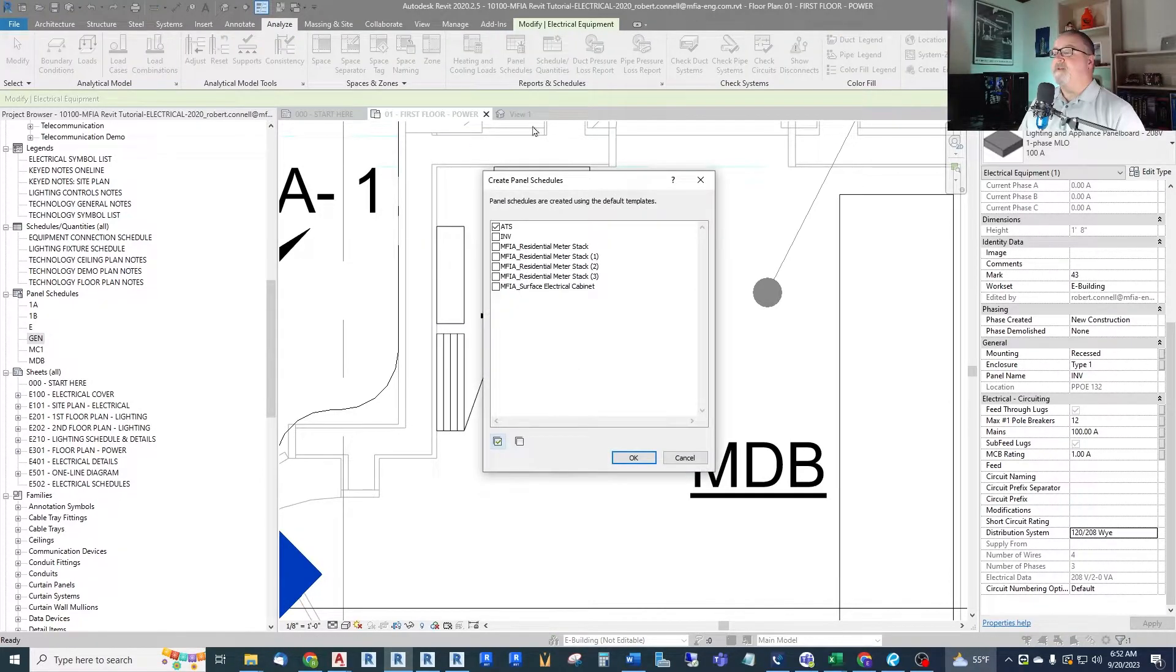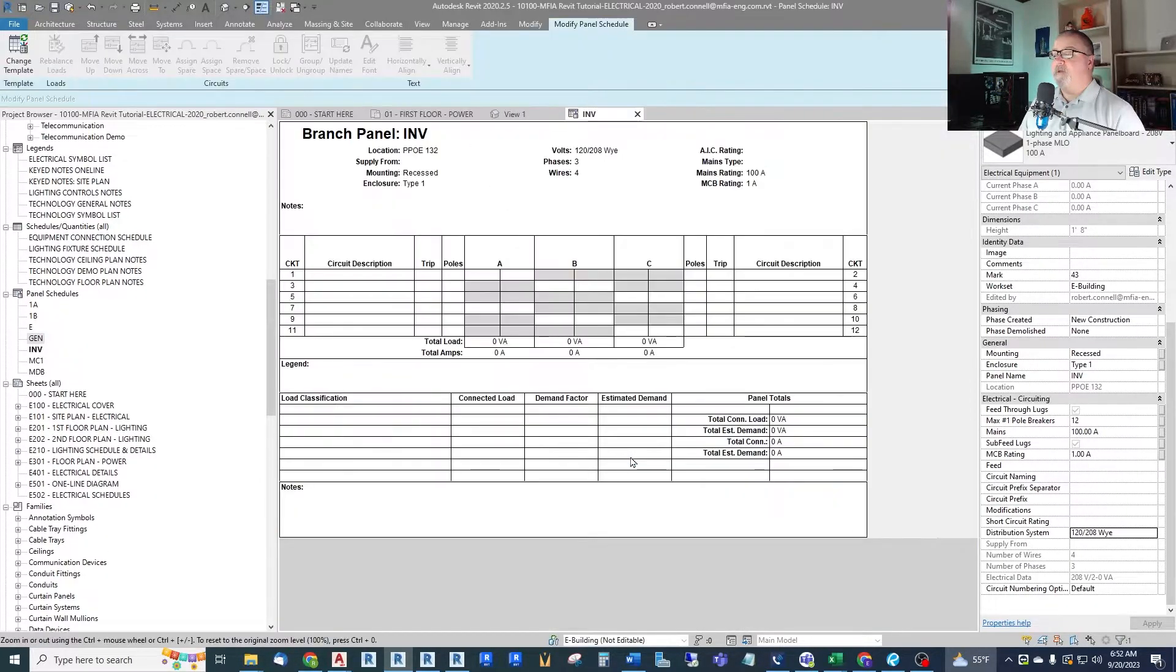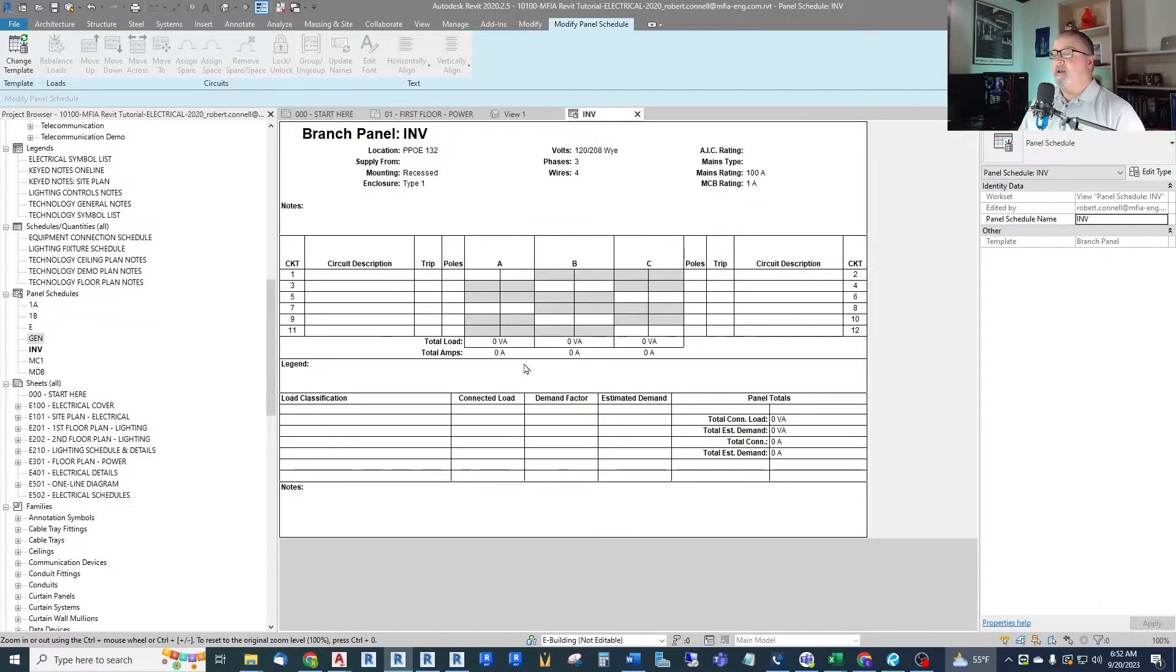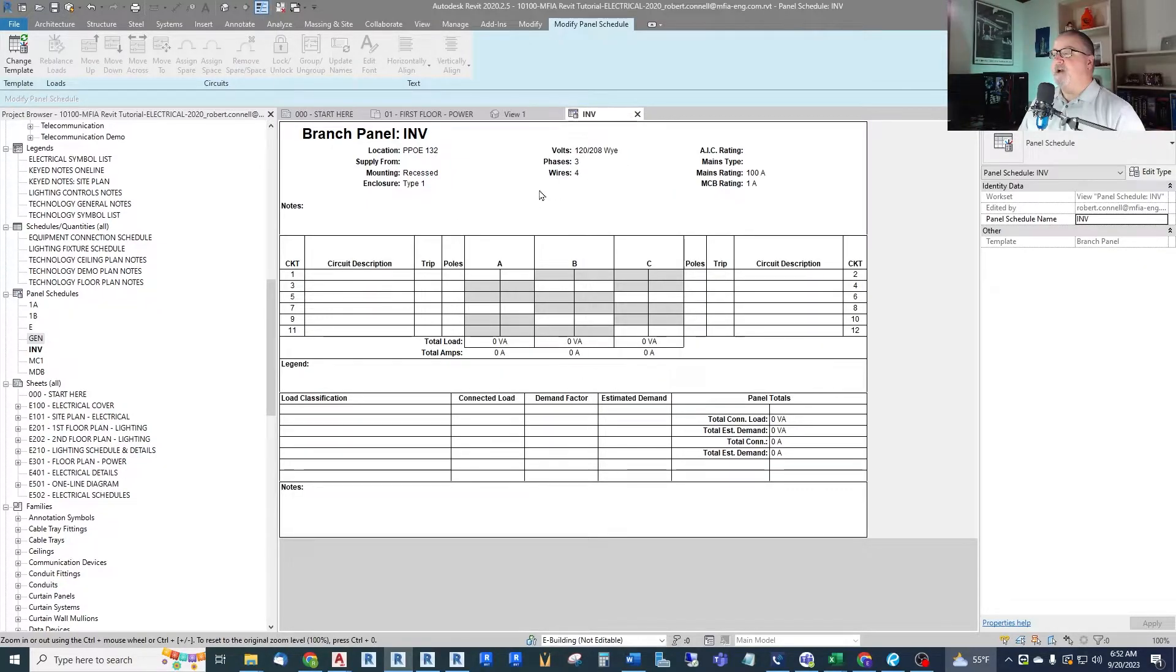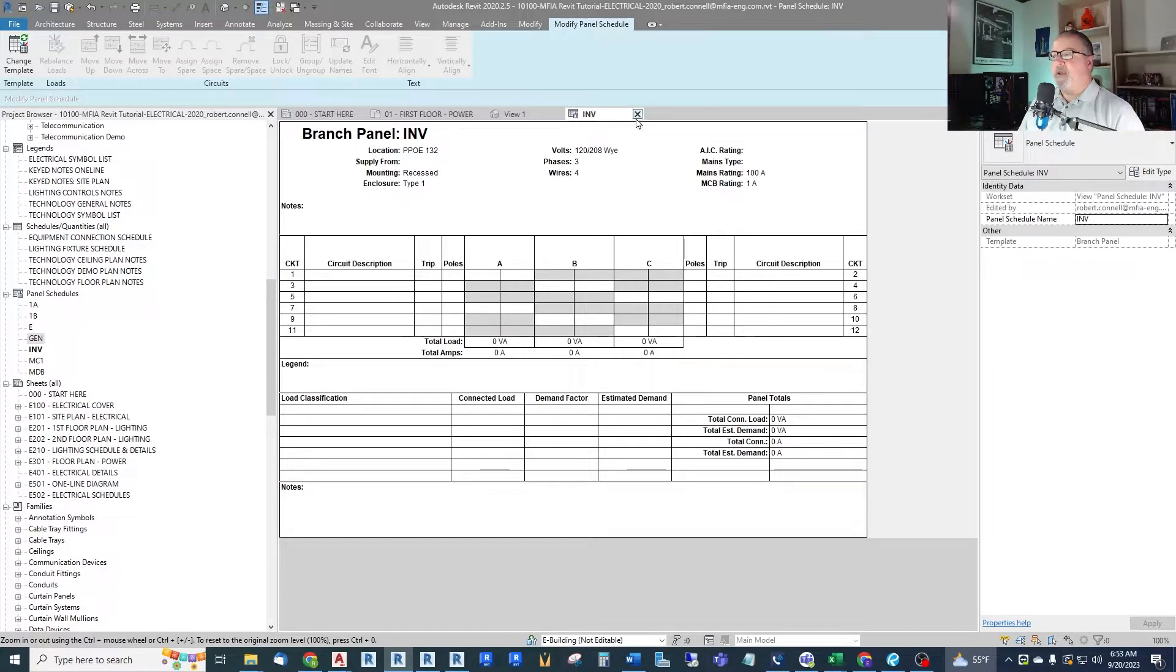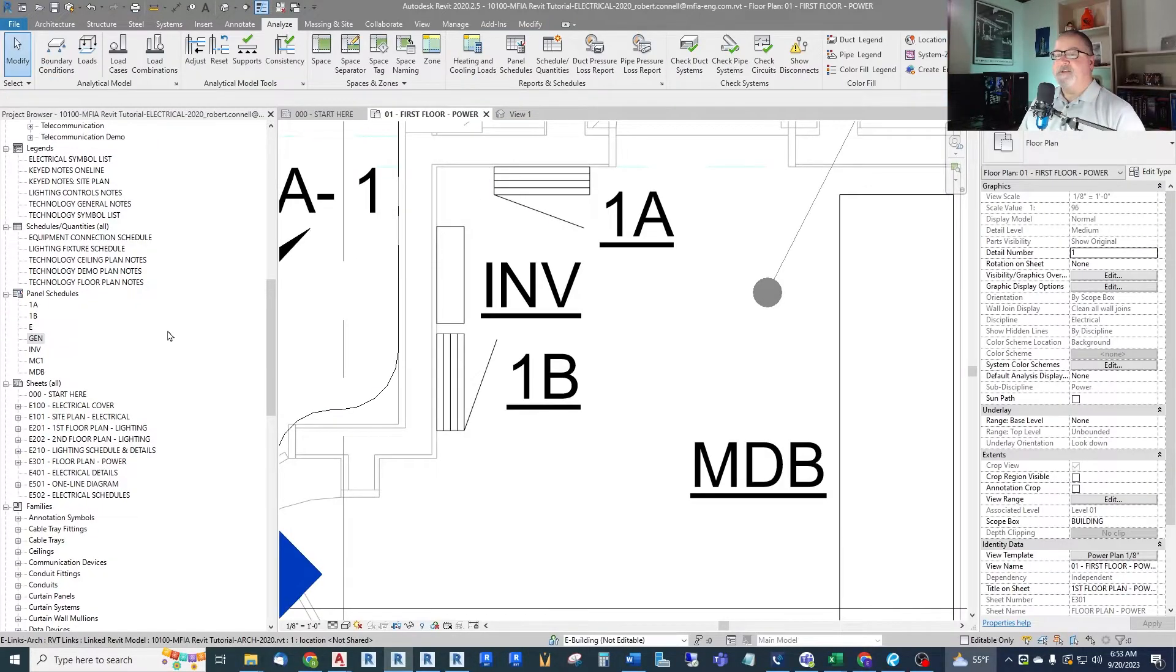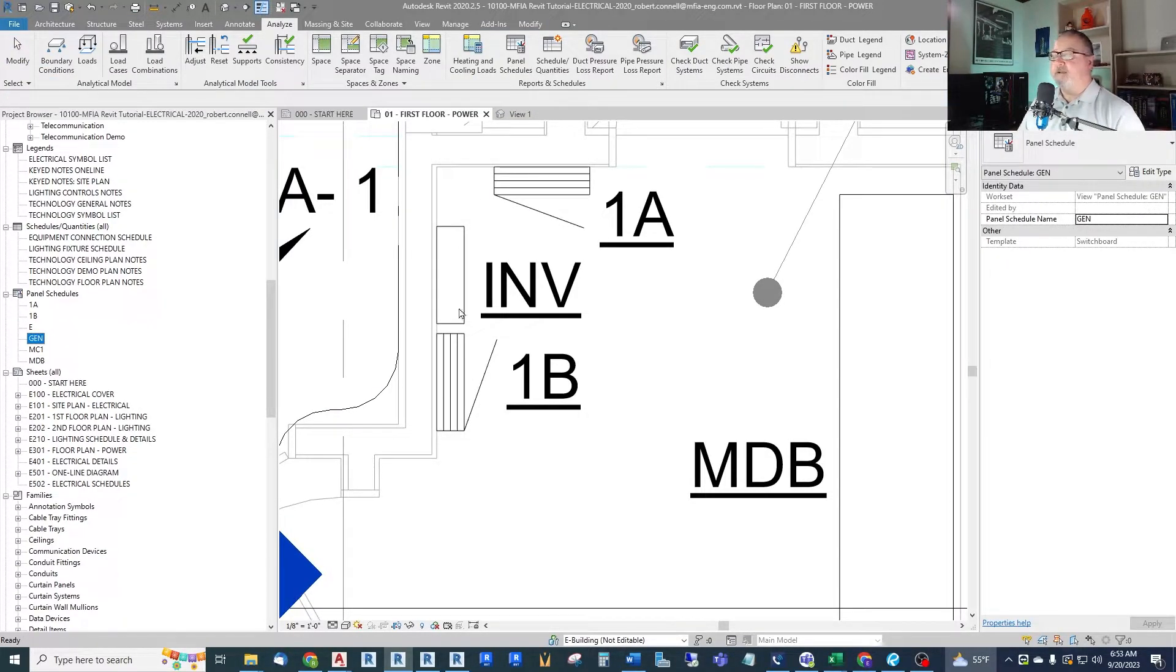If we go to panel schedule, create one for the inverter, we can see that it has given us all three phases. Three phase four-wire 120/208 Y and that is not what we want. So just setting the poles to two did not change us to a single phase panel. So how can we fix that? Well let's get rid of this inverter. Delete that panel schedule.